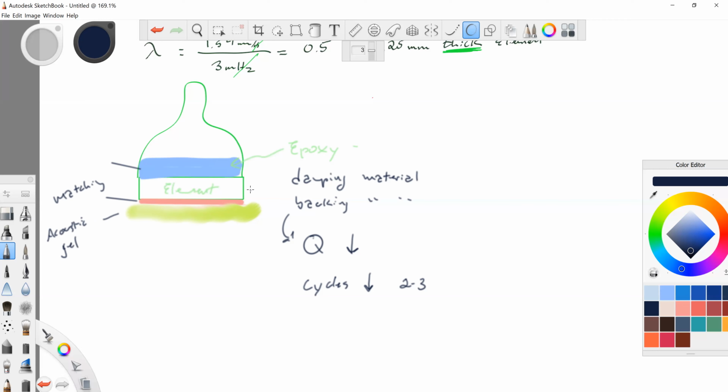The problem with the element to the skin level, we'll just call it tissue, is that the impedance difference is so great that, remember what happens, large impedance difference, very large impedance difference, sound comes down, sound bounces away, and very little makes it through. Not a good thing. So the matching layer is an impedance that is less than the element, still greater than tissue. It's a step down.